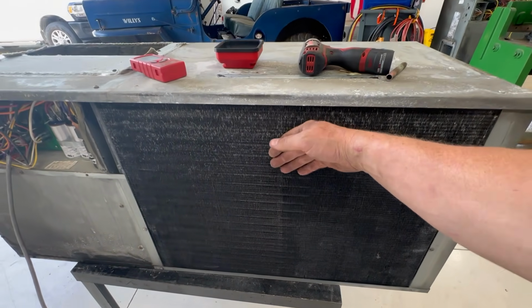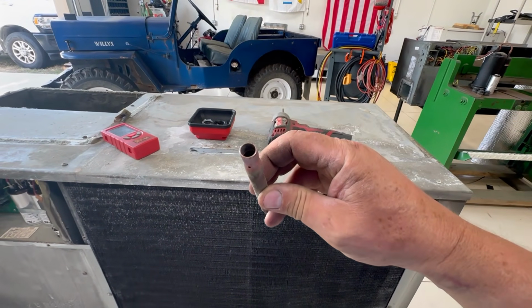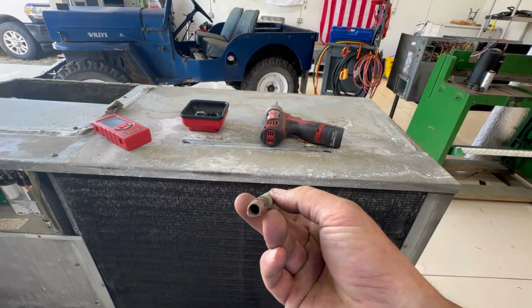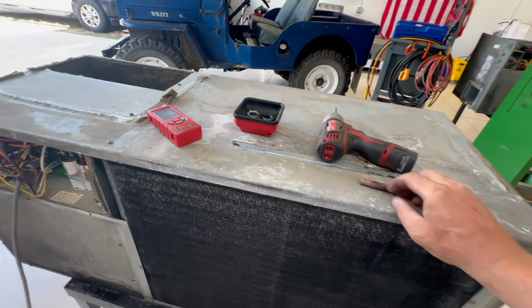So we've got good heat between the top and the bottom now. Just a plugged Bi-flo valve, had some trash up inside the little filters in there, but got that going, and 30 degree differential on that one, so she's cranking good now.